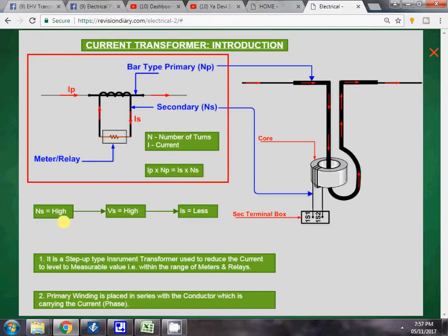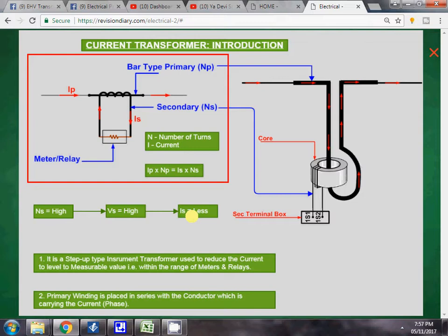The power remains the same: Ip × Np = Is × Ns. The current flowing through the primary multiplied by the number of turns of the primary equals the current in the secondary multiplied by the number of turns of the secondary. Since the secondary turns are very high, the voltage induced across the secondary winding is also very high. Because power is the same and voltage is high, the current in the secondary winding becomes less. In this way, we have reduced the high primary current to a low current in the secondary winding. This is the definition and working of a current transformer.